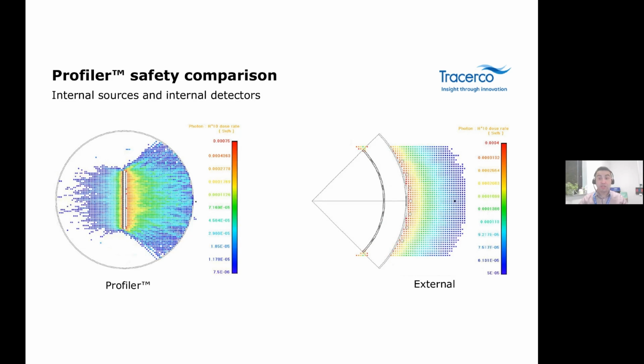So when we look at using a low energy gamma profiler versus a high energy external detector system on the right, we see the profile results. No additional dose is on the surface of the vessel. For the external system to work correctly, there must be dose rate in the oil so that the interface can be differentiated. It is also important to note that the external detector system cannot perform with high accuracy when the vessel is not flooded. They require reducing the activity of the sources that would normally be in air, so as to avoid a high dose rate on the vessel wall. However, those are external, and if the interface level increases, the activity is not high enough. There is not enough to differentiate between oil and water.